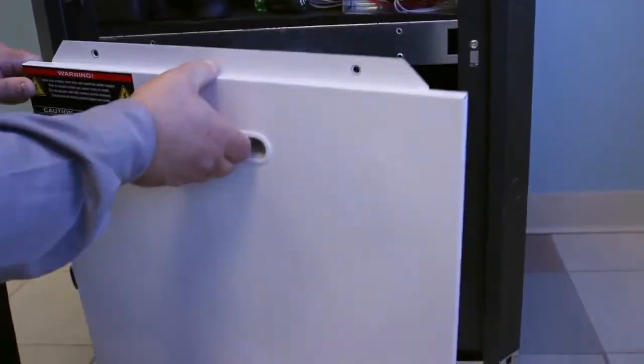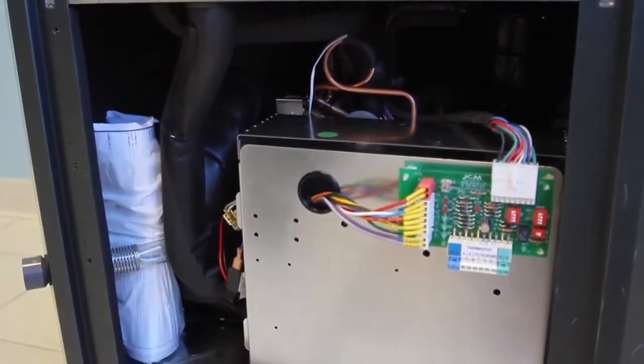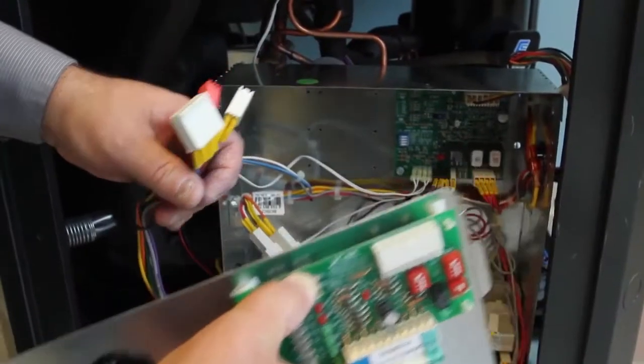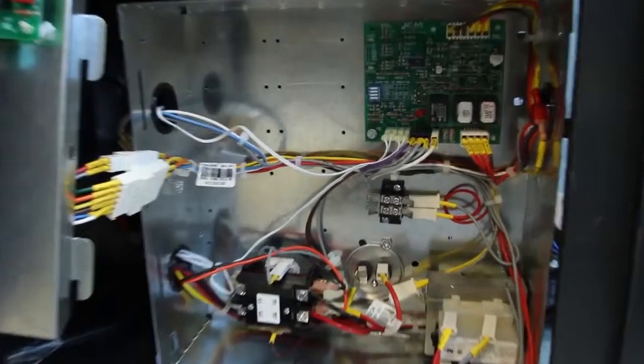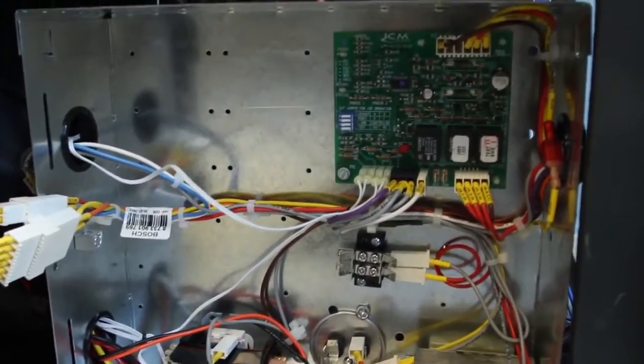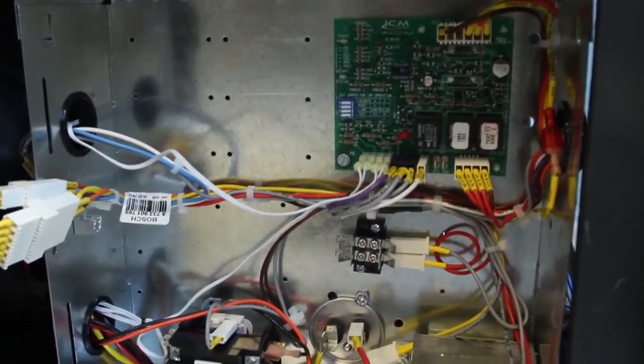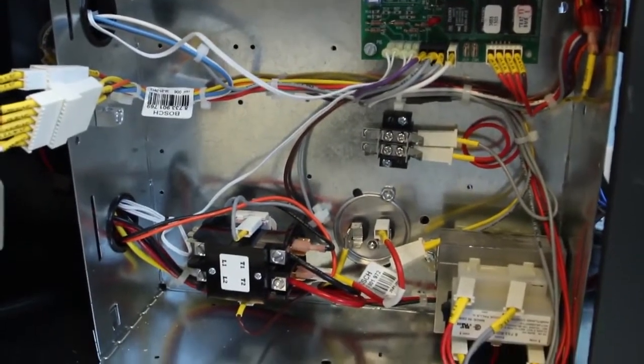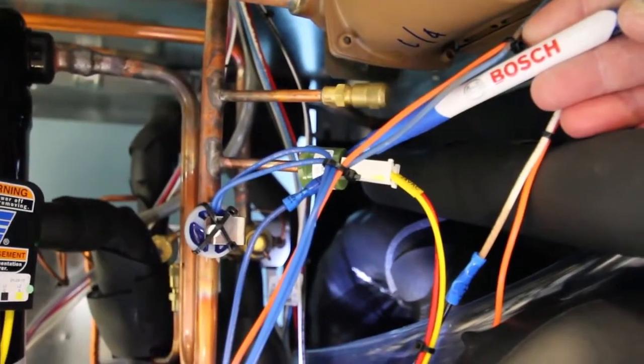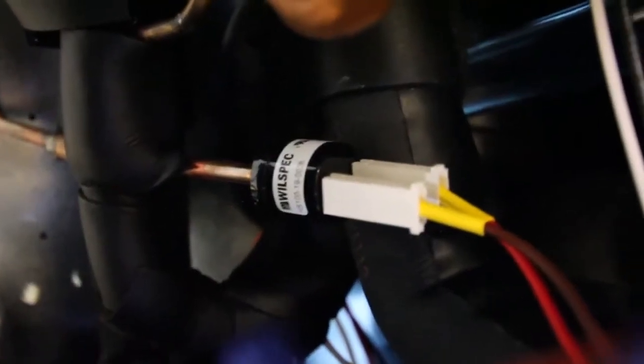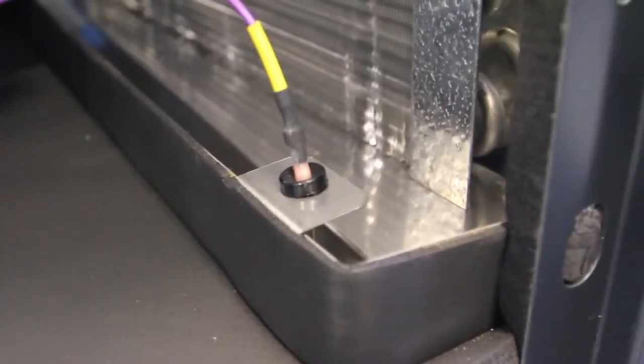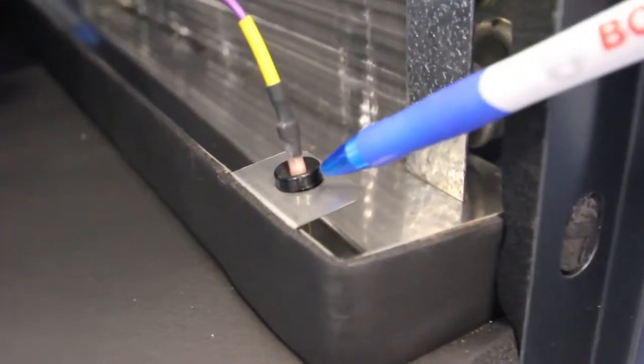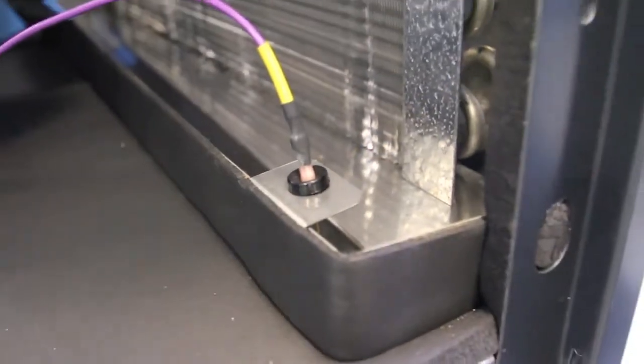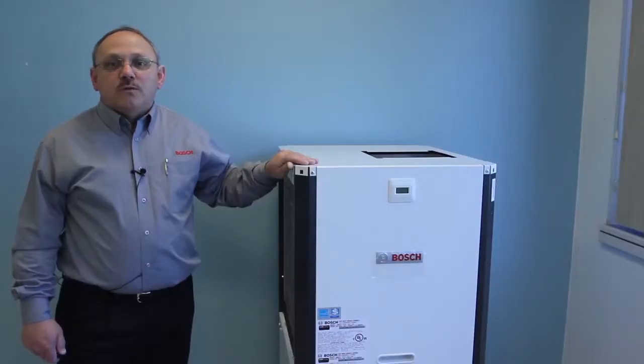Like the TA series, the SM is equipped with a unit protection module or UPM board. The UPM monitors safeties, controls compressor operation, and reports faults. The standard safeties include low and high pressure switches located in the refrigerant lines and condensate overflow protection. Two great new standard features are water coil and air coil freeze protection.